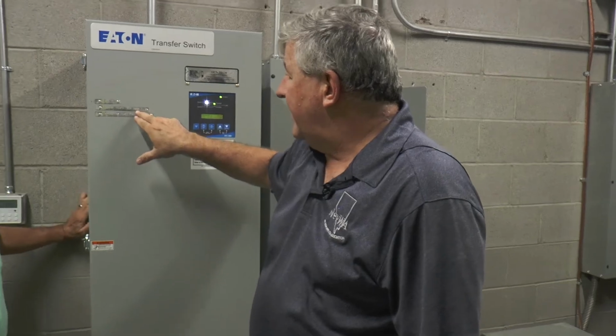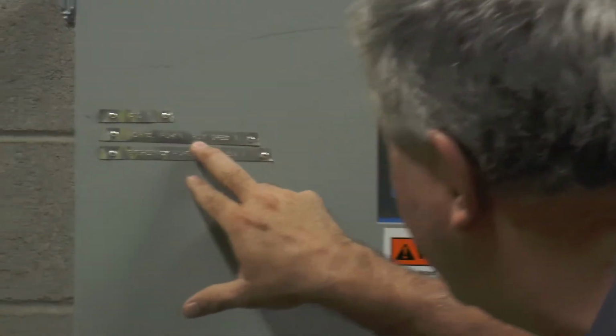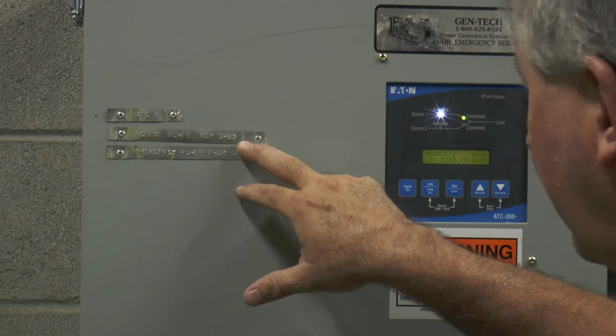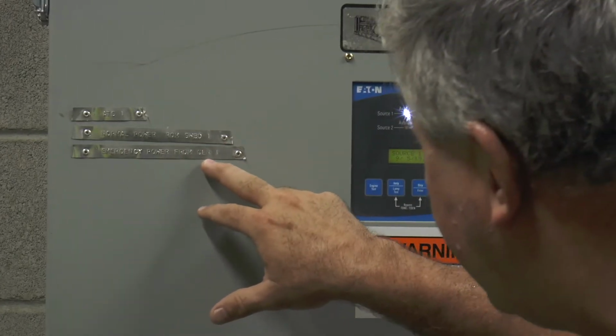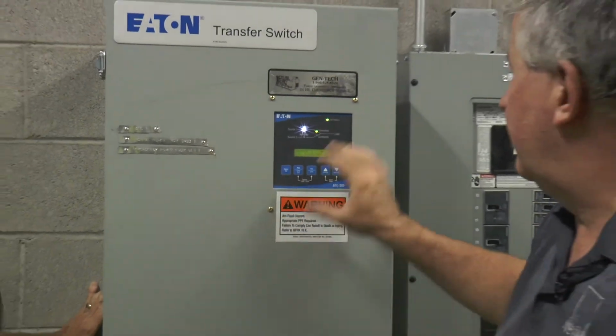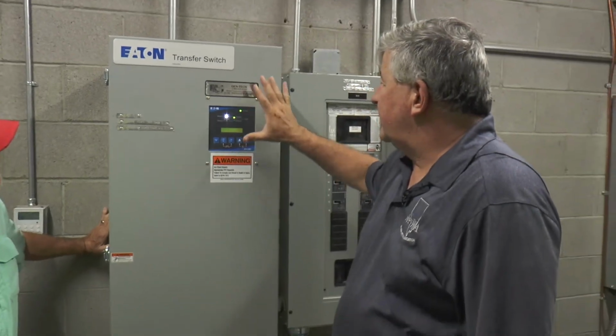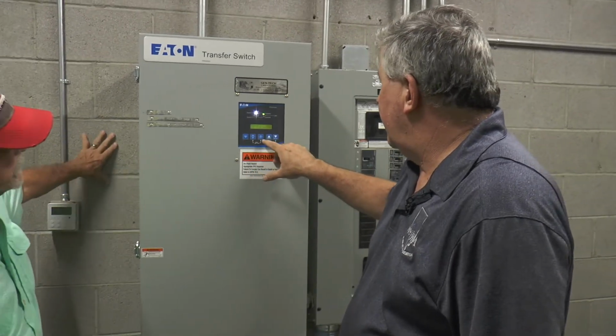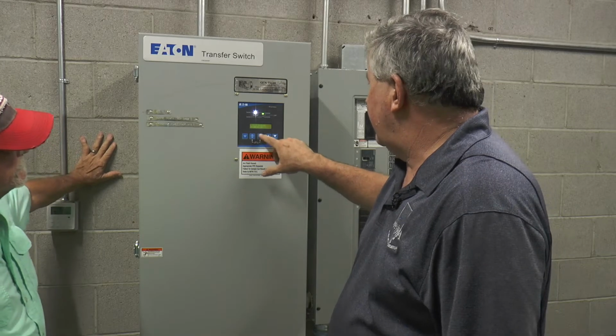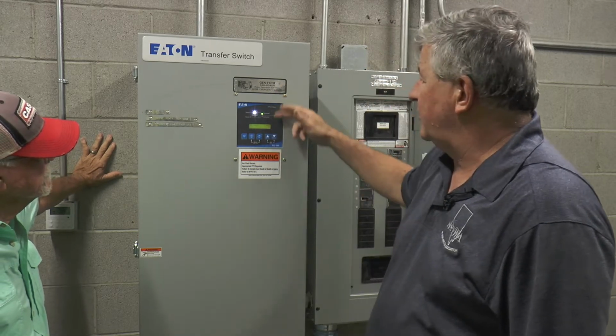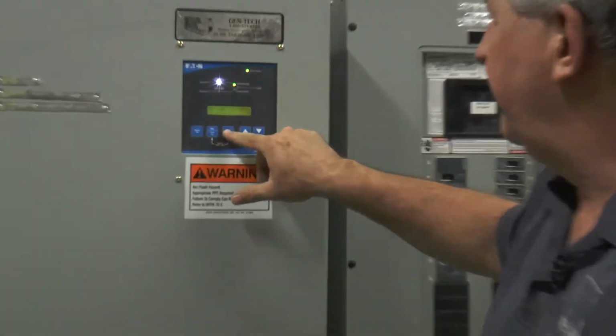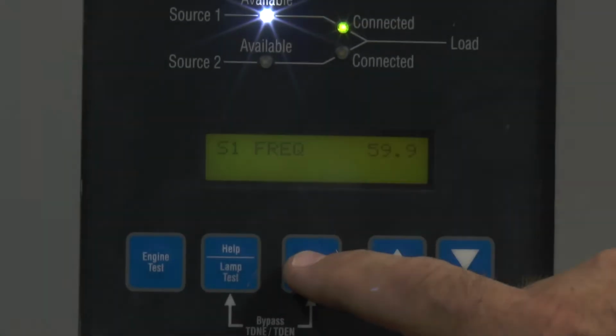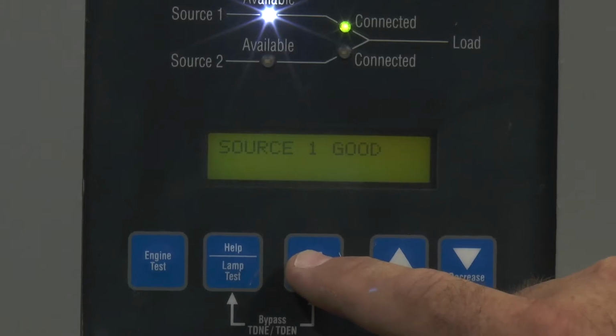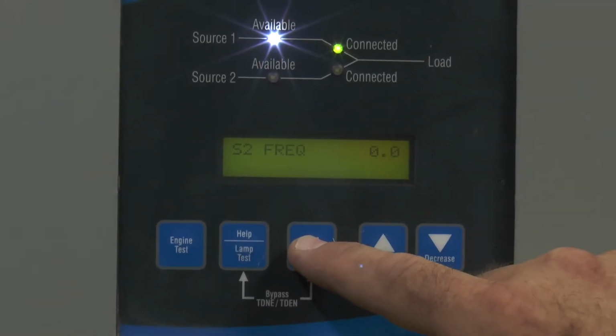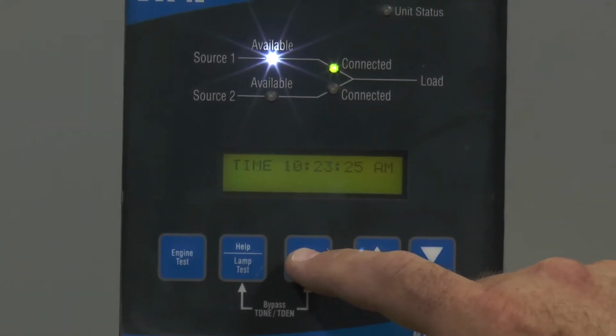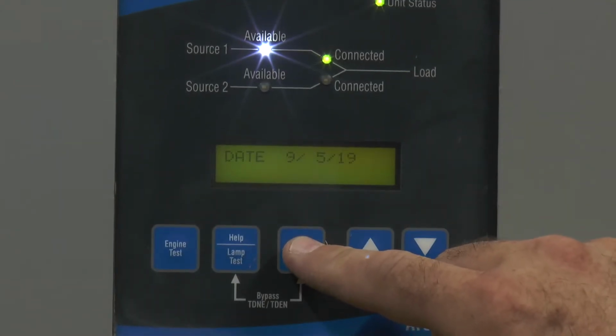They have identified normal power being fed from room switchboard number 1 and emergency power from generator number 1 in the other room. Controls on this generator set are set up here. You can arrow down, enter, and it gives you system voltage, and there's a menu of keys going through. System voltage for source 1, frequency, source 1 is good. Source 2 is 0, which is the generator set. It's not running. Time and date are stamped here.